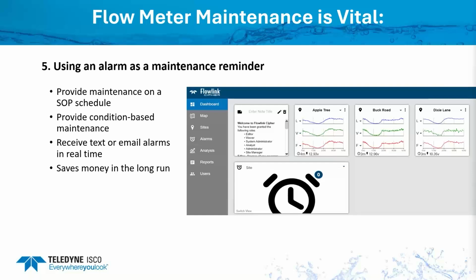Now, you do have the option of using alarming as a maintenance reminder. I've talked about several things that can determine when there's an issue, either level or signal strength, even temperature. You can use your software and have the data pushed out to cloud-based software where you can quickly look at it, and then you can do your maintenance based on the conditions instead of just going out there on a regular basis.